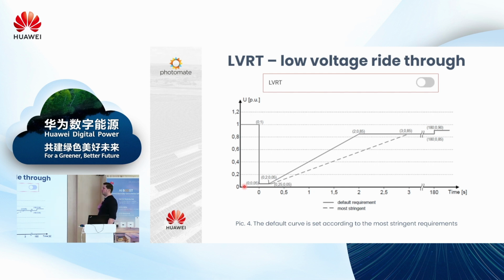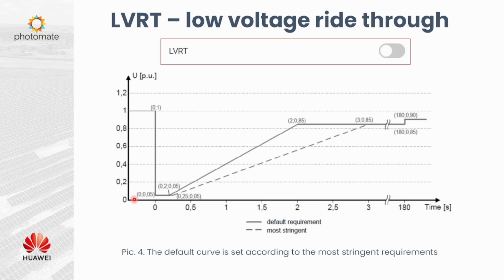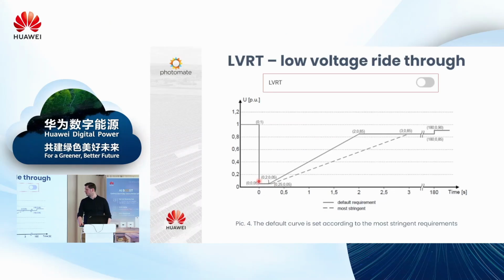So low voltage ride through is this function, and the opposite function is the high voltage ride through. Our inverters, not only ours, but I would like you to understand when and how you can use it, are able to work with the grid even if you have some voltage dips or spikes. It can withstand this for around a few seconds. This characteristic shows how the voltage is dropping almost to zero, and then the inverter is trying to rebuild this voltage.